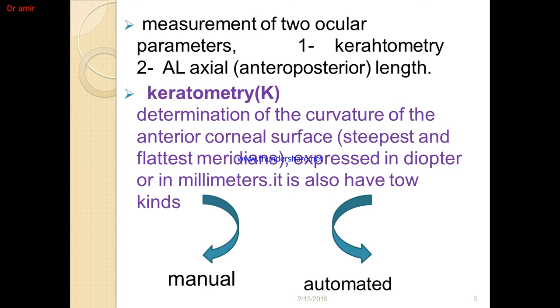So why do we have some error in the measurement of the corneal power? Because the power of the cornea is most accurate just in the center of the cornea, about 1.5 millimeter. But our instruments, like the manual one, measure the cornea from 3.2 millimeter, and another one from 1.6 millimeter to 5 millimeter. Because the central area is steepest and the peripheral area is flattest, we have some error in the measurement of keratometry. We also mentioned before that we have two types, manual and automated keratometry.